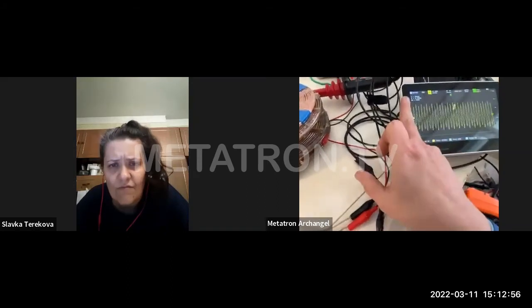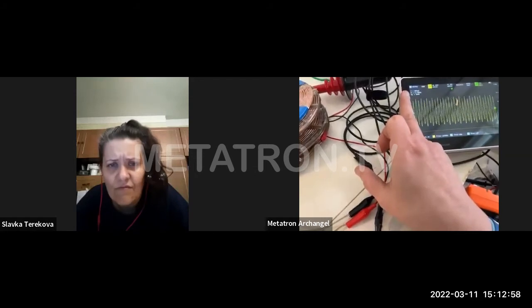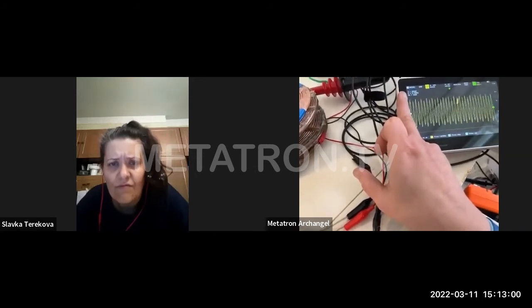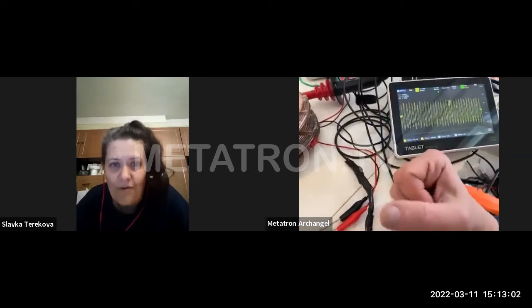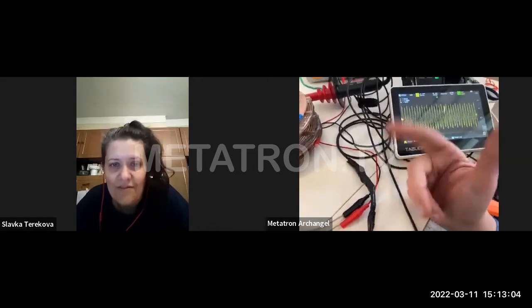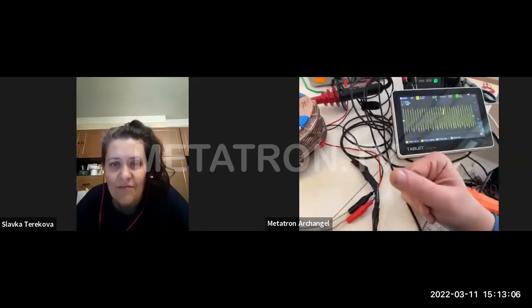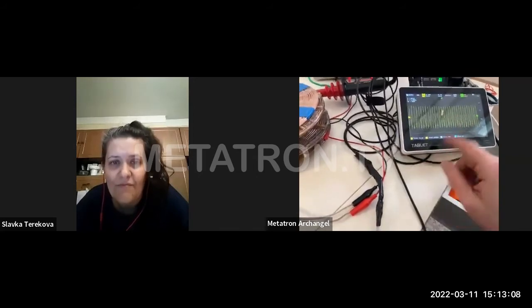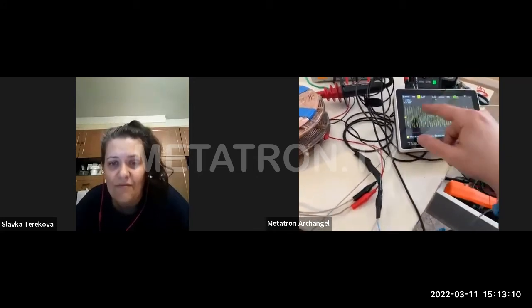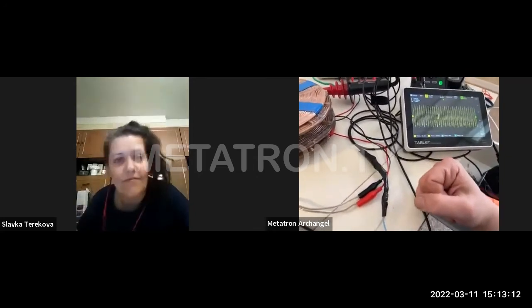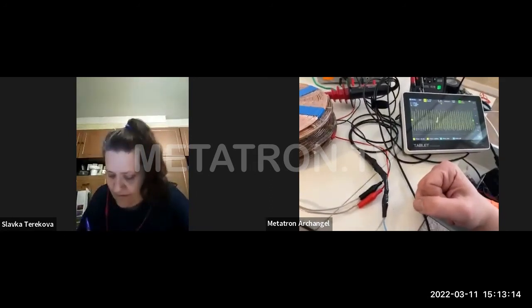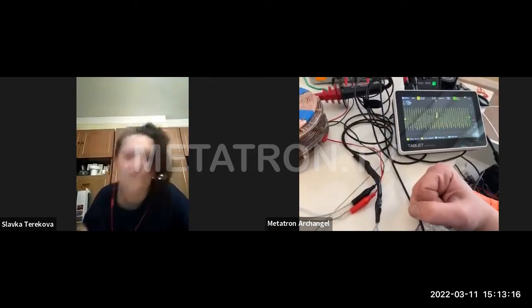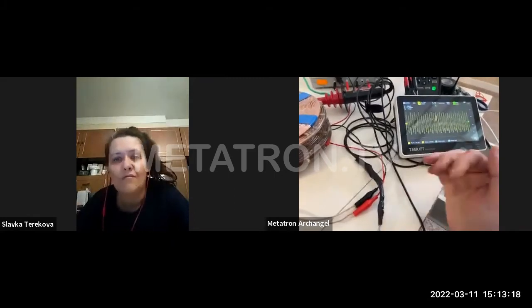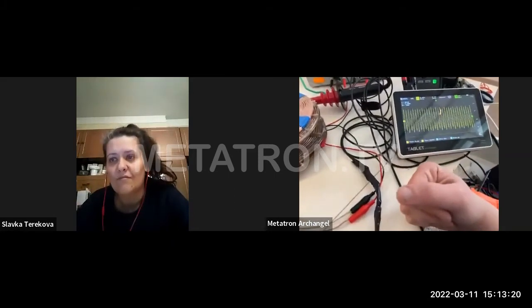And as you can see, now we have 333 volts. That's interesting, by the way. It has to be times 10. The reason is the multiplication on this input is only 100 times maximum, not 1,000 times. So it's showing it 10 times less, so you have to multiply it by 10.